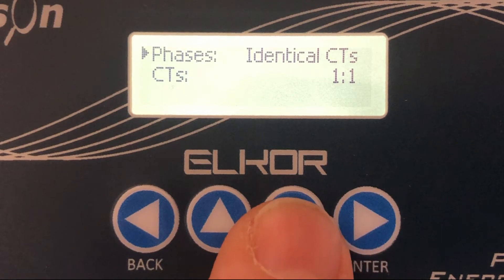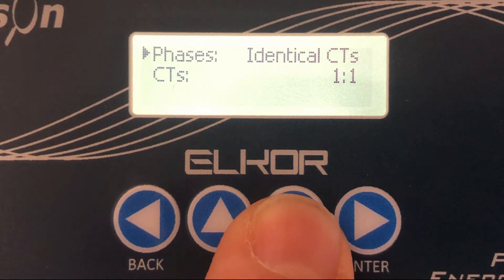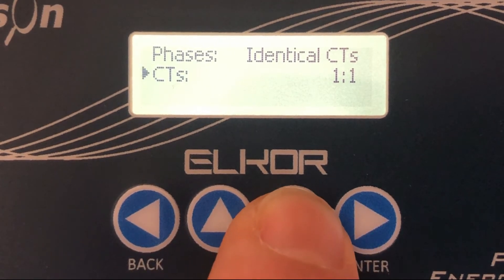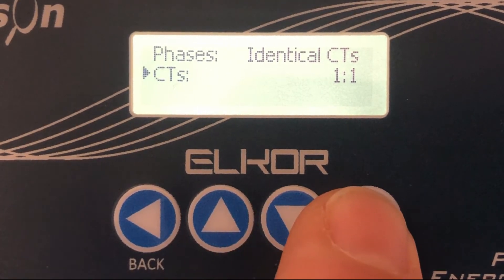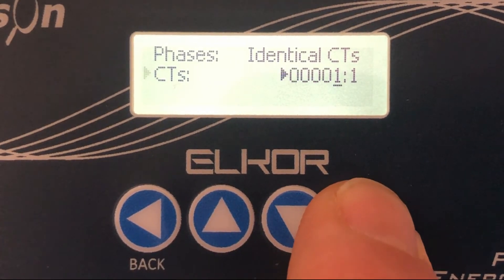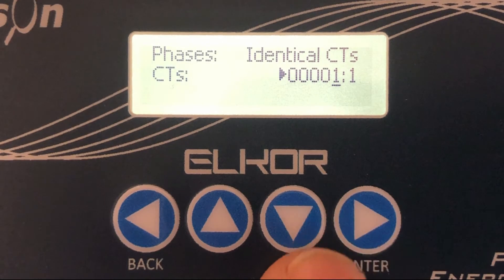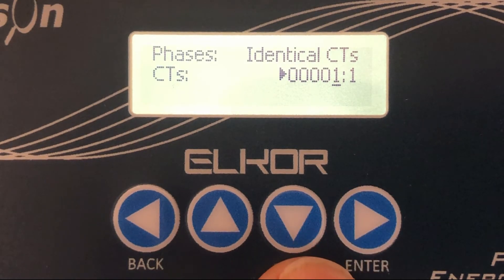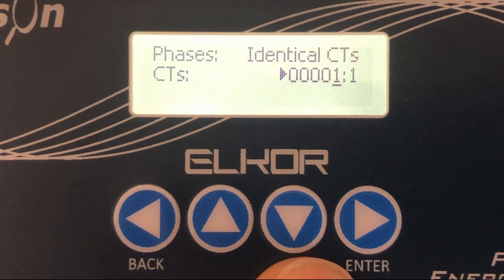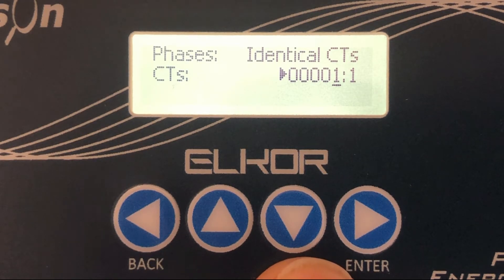Use the down arrow to select the CTs menu option and press enter to edit the values. We start by entering the CT ratio primary. In this demonstration we'll assume that the CTs are 2500 to 5.